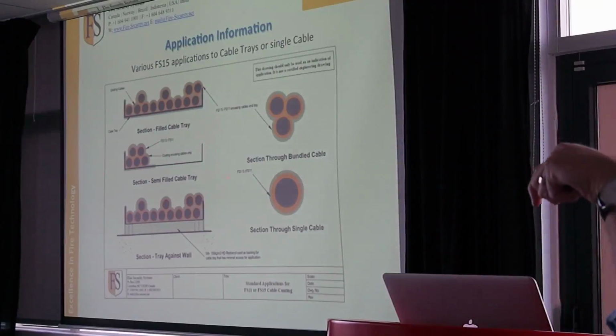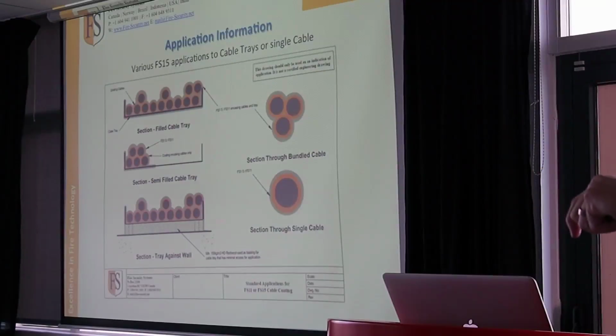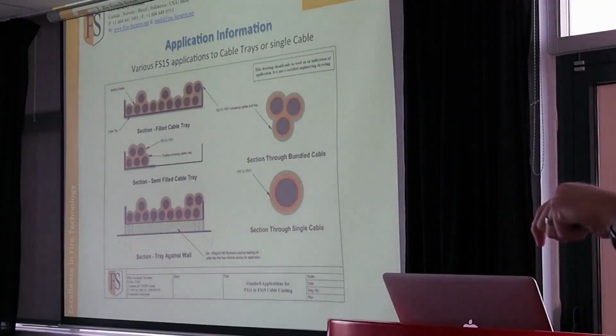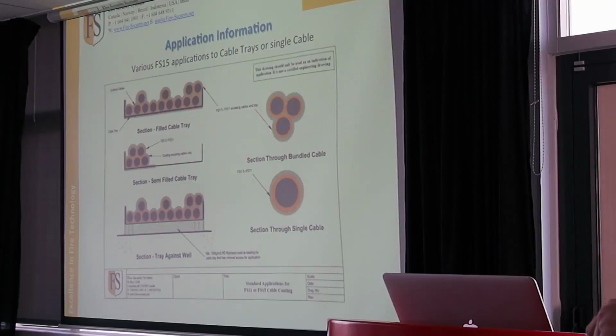When cable trays are against walls that you can't get access to, we will fill the back of it with rock wool and then spray down the sides here so there's no fire ingress into the rock wool. That means that there's no cable coating at the back of this tray. But that doesn't matter, because what you're doing once again is stopping the oxygen from being in there. So once that's stuffed in there, there's zero oxygen, which means that there's zero flame spread again.